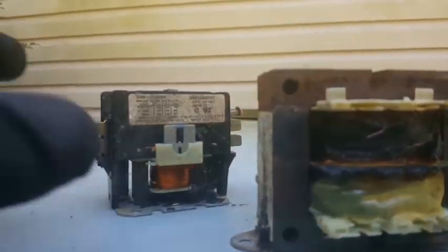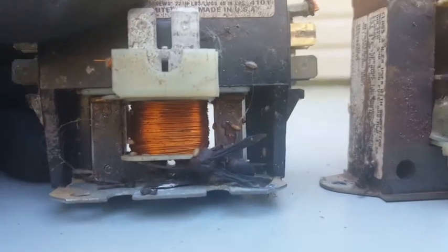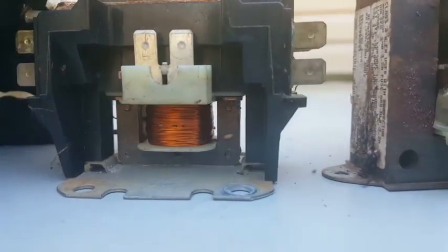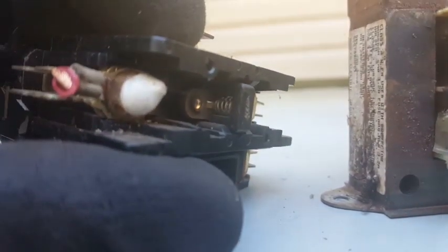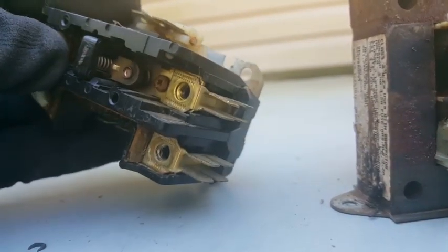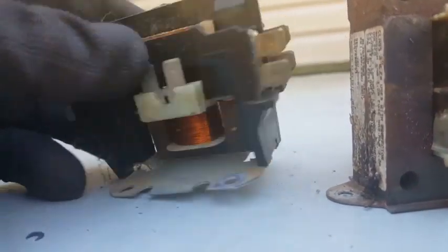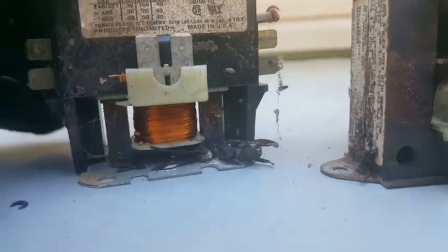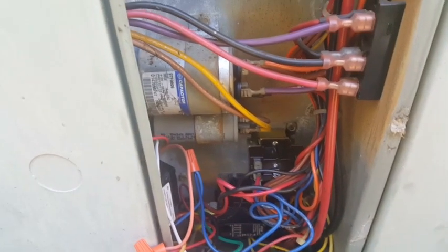Contactor is mounted back in place. One screw on the top left, one screw on the bottom right. All the wires matched up verbatim. Here's our contactor. Comes with some creepy crawlies on the bottom. Overall, points look a little bad in there if you can see them. But the coil is actually pretty shiny. Just comes with a few bugs on it. So we're going to get those capacitors switched out, and hopefully this thing will breathe again.